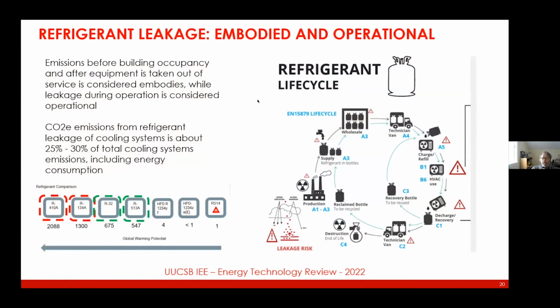Just wanted to talk a little bit about refrigerant leakage, something that's overlooked, but there are some studies out there that indicate that the CO2 emissions from refrigerant leakage of cooling systems is about 25 to 30% of the total cooling system's emissions over the life of the system, which is a big deal. And so addressing this whole life cycle refrigerant leakage issue: what happens when you originally make it, when it's originally transported, when the equipment is charged, what happens during servicing, during the life of the equipment, and then what happens to the refrigerant when the equipment goes out of service. Very big, very important issue for CO2 equivalent emissions.